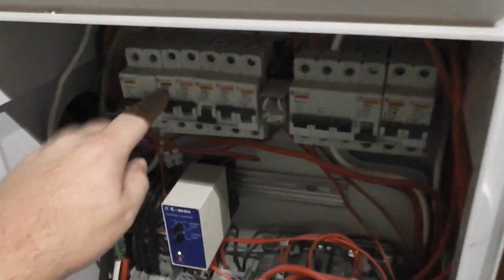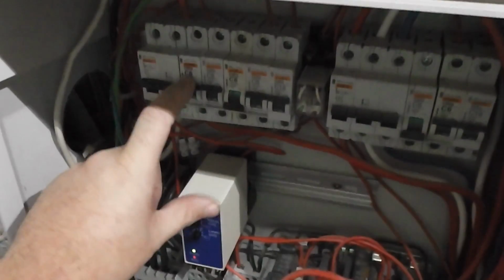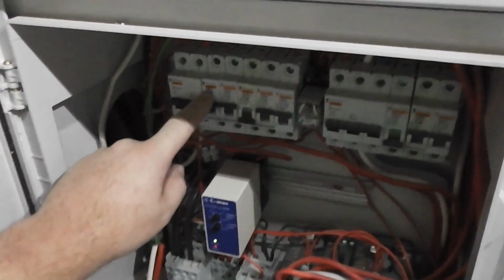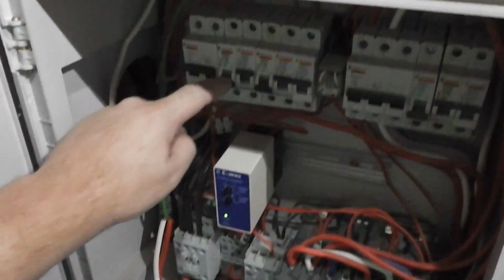To actually do a test run, this circuit breaker here is the feed into that. So to make it think there's a power cut, all I do is kill the mains feed to it, like that. The generator now thinks the power's off, and will wait 10 seconds before doing anything, then it will start.